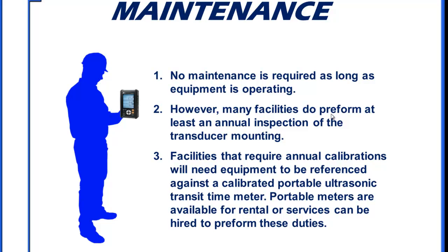You can rent a portable ultrasonic transit time flow meter from us, or have us come to the site to do an annual inspection, so it's a side-by-side reference there. Or you can hire local services or rent the device and monitor it yourself. So if you do need to field calibrate it, really not that much of an issue. It's more field verification, and that's the case there. We can provide you with the equipment, either rental, purchase, or you can use local services to do the same thing to answer that particular question.